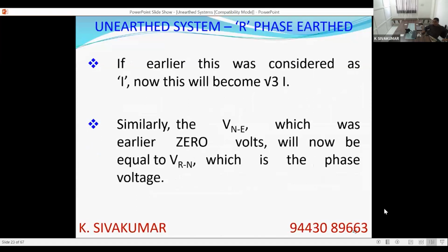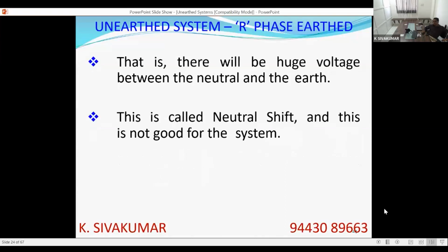Also, earlier neutral and earth were at the same potential, so there was 0 volt between neutral and earth. But earth is now R phase. So the neutral-to-earth voltage will be the neutral-to-R voltage. So neutral will show phase voltage now, because earth is R phase now, and the voltage between neutral and earth will be the voltage between R and neutral, that is, phase voltage. So the neutral will shift itself. There will be a huge voltage difference between neutral and earth. Neutral will shift from its 0 voltage to a value equal to the phase voltage. And this will create its own set of problems.